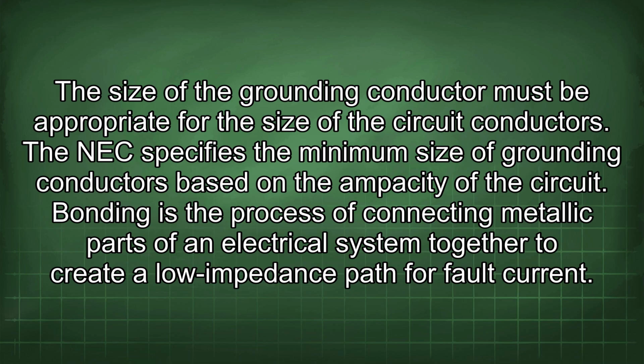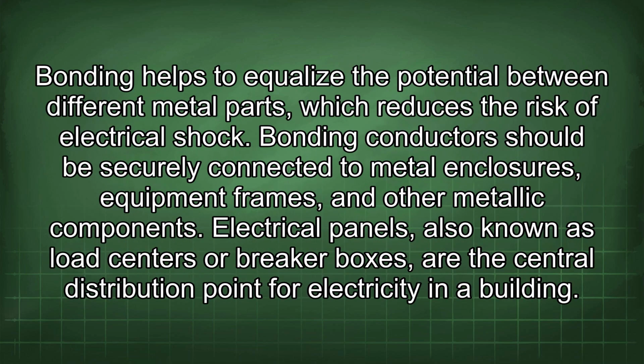Bonding is the process of connecting metallic parts of an electrical system together to create a low impedance path for fault current. Bonding helps to equalize the potential between different metal parts, which reduces the risk of electrical shock. Bonding conductors should be securely connected to metal enclosures, equipment frames, and other metallic components.